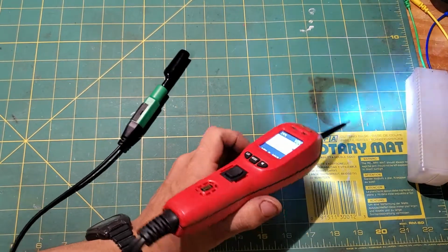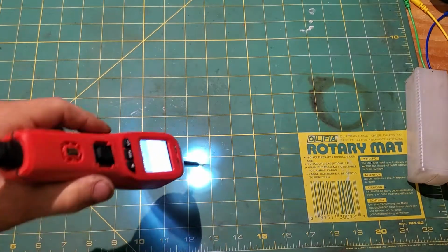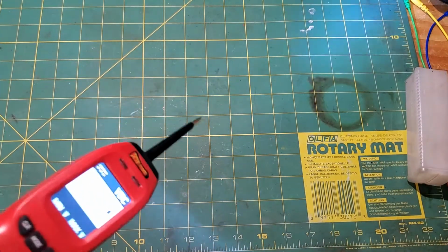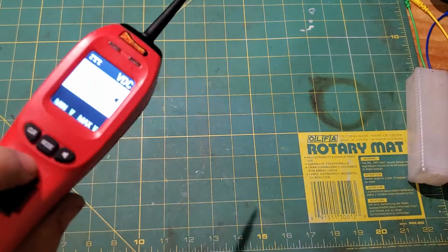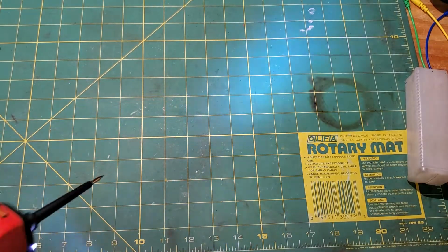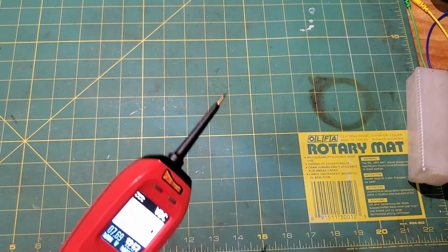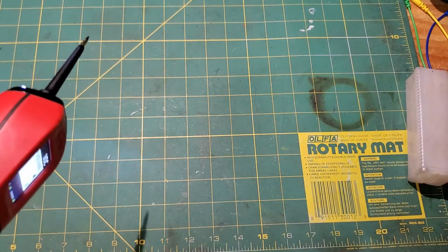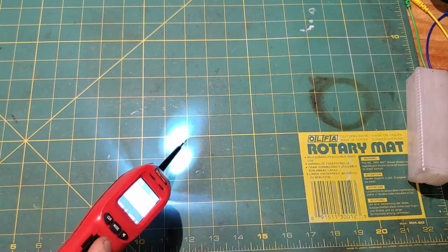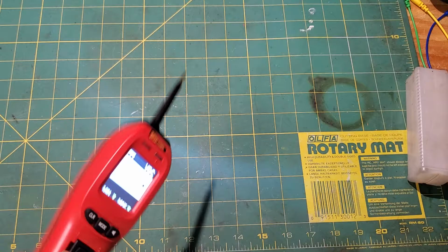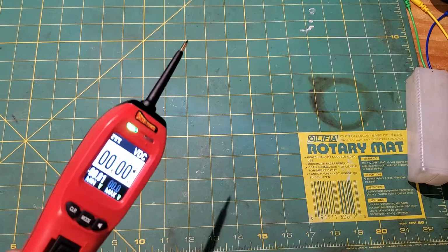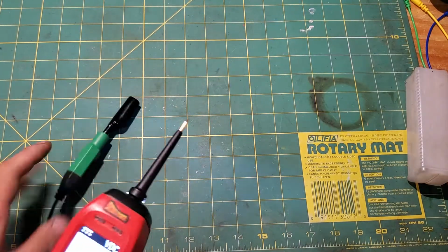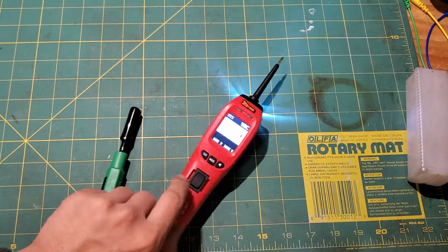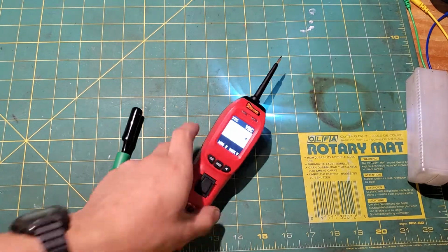The nice thing about this is you can quickly check fuses and see if they're ground or power just by listening. Touch both sides of a fuse - if you hear it on both sides, you have power on both sides. If you hear it on one side and it's open on the other, you have an open fuse. If you hear it on both sides on the ground setting, it's a ground fuse, and same thing - if you don't hear it on one side, it's open.